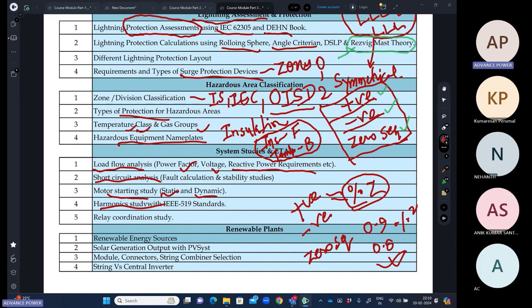We will see what are the orders of harmonics there when we use the different pulse rectifier equipments. After getting that, we'll also see how smooth the sine wave is when we are going for 12 pulse or 24 pulse rectifiers. Then we'll use the filters. Capacitor banks and filters will be used to nullify the harmonics. Capacitor banks will take care of your reactive power requirements, and your filters will take care of the harmonics which are there in the system. Sometimes we use active filters also, passive filters also. So that concept we'll discuss in detail.